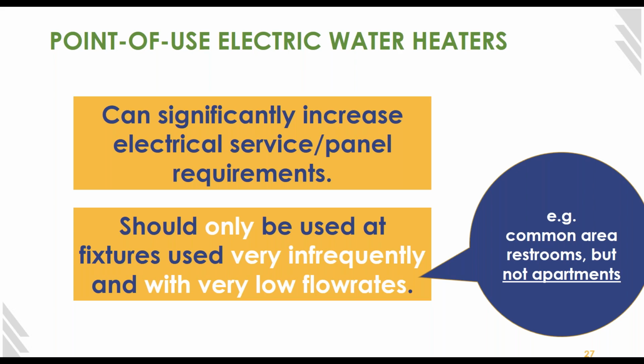So really the only reasonable place to use these is for fixtures that are used very infrequently and with very low flow rates. Sometimes we see these used in very efficient buildings for a bathroom in a common area way on the other side of the building, connected to the faucet so people can wash their hands without freezing cold water, and that fixture gets used rarely. It uses a lot of electricity to heat that water, but it's heating so little water that it doesn't have a big impact. So common area restrooms could be a reasonable use case for these, but not apartments, certainly.